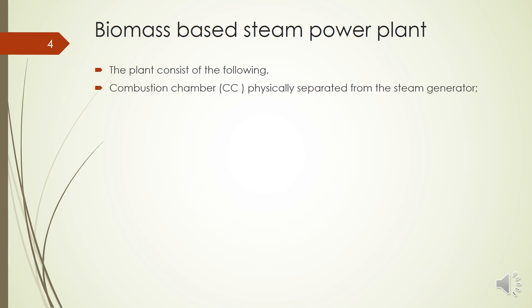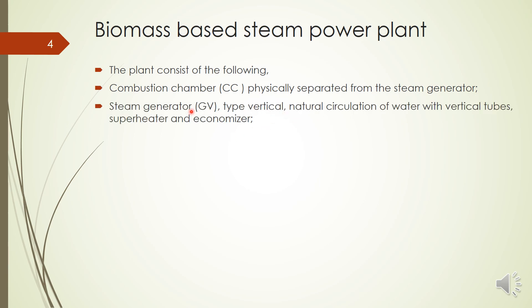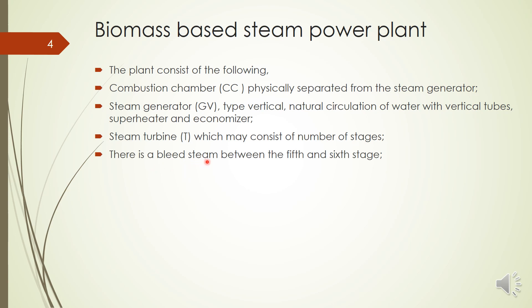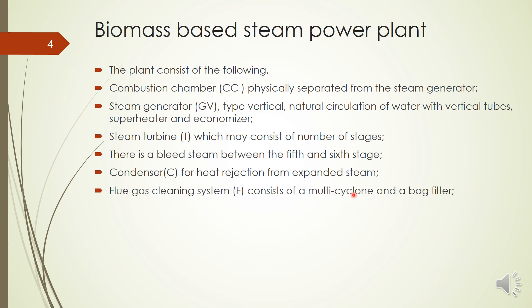The plant consists of a combustion chamber, which is separated from the steam generator. The steam generator is typically a vertical natural circulation boiler with a superheater, economizer, and other accessories and mountings. The steam turbine consists of a number of stages — normally expansion takes place in more than one stage for better performance. Steam is bled between the fifth and sixth stage — if there are ten stages, steam is bled mid-way and mixed with the feed water. A condenser is used for rejection of heat.